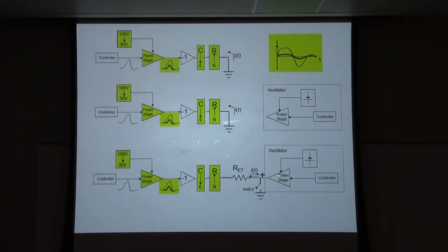So we have to allow for the lung to empty. So what all ventilators have is, when it is the positive phase, they are pushing pressure, they have to close that switch to the ground so that all the current goes to the patient. And when the cycle is finished, according to the controller, it says stop now, don't give more pressure. So the pressure disappears and the switch opens to the ground so that the patient can empty his lungs.